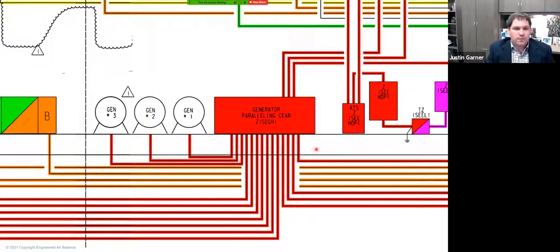It may be a second feed from your utility. It may be generators, as we have here, or it may be UPSs, which I'm going to talk about in a moment, things like that. But it's important to understand, if you do have multiple sources, what is being fed potentially by dual sources. I'll talk about that a little bit more in a bit, why that's really important. But just recognize here that we have generators being paralleled, meaning that they are feeding into a common piece of switchgear that controls them and makes them all get in sync, or parallel. And then that's distributed out.